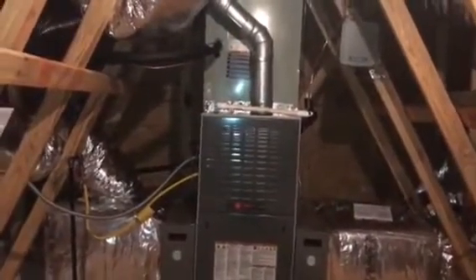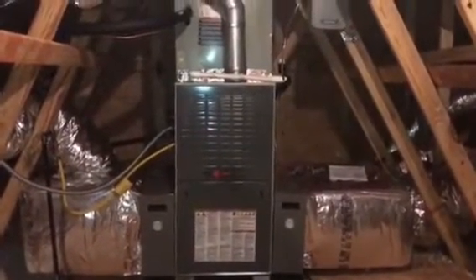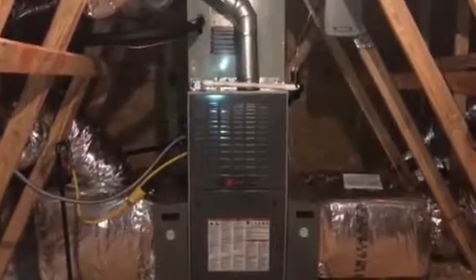Everything should be looking completely different now. We have a nice Trane variable speed furnace. Got our actual zone system installed — there's the zone panel, here's our static pressure transducer, here's our fully modulating dampers. There are the sensors for temperature as well as static pressure, with the static pressure sensor in the return. And we've got these nice cabinet-type filters.